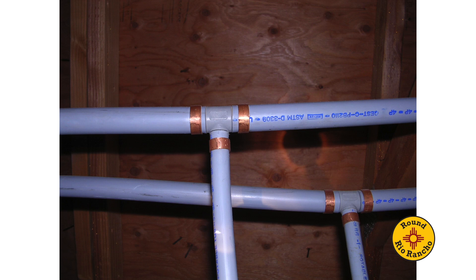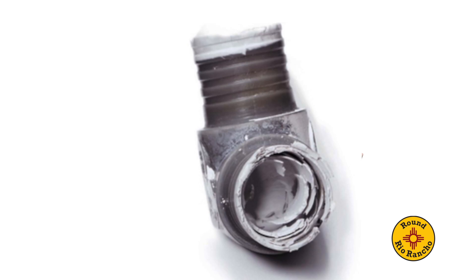The primary failure in plumbing systems in the AMREP homes changed from failures at the crimp connections to mid-pipe failures, often inside walls or under concrete slabs. The theory is that chemicals used to disinfect city water cause a breakdown in the material. The pipes flake and disintegrate from the inside out, making it impossible to know where a failure will occur.